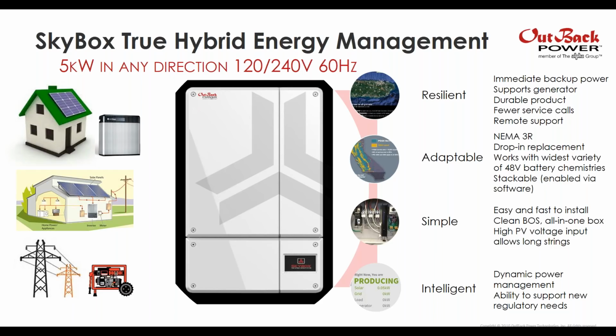By adaptable, we mean that it's NEMA 3R, so it's a drop-in replacement for any existing grid-dependent string inverter. It works with the widest variety of 48 volt battery chemistries, all of your traditional lead acid batteries, as well as many advanced lithium ion battery chemistries. And it's stackable, which will be enabled via software down the road.